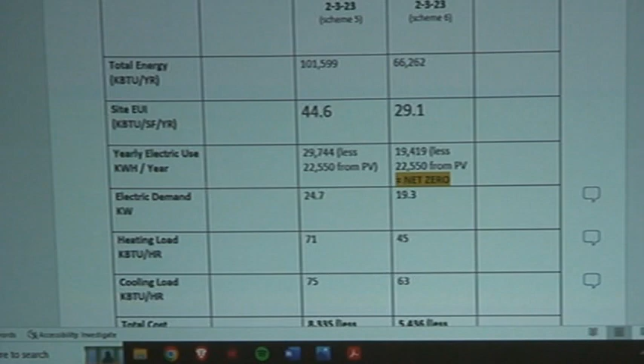The program calculates this, even though it tells us not to use it for sizing heating or cooling equipment—that's not what it's made for, but it still gives me that information. So 71,000 BTUs in the first version, 45,000 BTUs for heating in the next building. That's a nice savings—it means I can buy smaller equipment, lowering the capital cost and partially offsetting the cost of the insulation. Cooling load, not surprisingly, is about the same as the heating load, and in this version the cooling load is just about the same as the other version, so that doesn't surprise me.